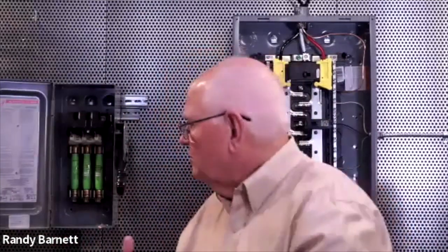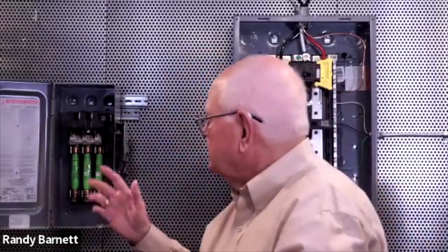Now, as a qualified person, I can enter this limited approach boundary area and do some work. But if I get any closer than 12 inches, the table 130.4E says if I get within 1 foot, that is the restricted approach boundary. The restricted approach boundary is based on electrical characteristics at 480 volts phase to phase, and electricity can jump out through the air and cause an arc. And also there's inadvertent movement. I could be in here doing some work and accidentally move and touch something I shouldn't.